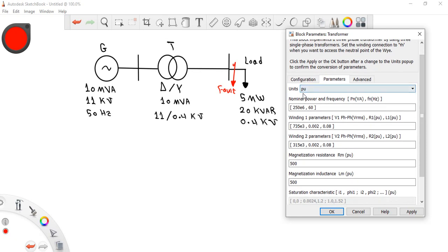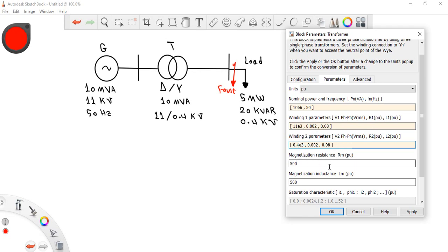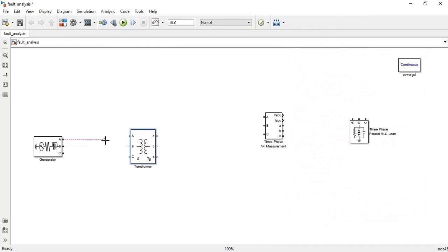In the parameters tab, set the nominal power to 10 MVA (10e6) and frequency to 50 Hz. For winding one, the line-to-line voltage is 11 kV, and R1 and L1 are kept at default values. For winding two, the line-to-line voltage is 0.4 kV. Keep the magnetizing resistance and inductance at their default values. Click Apply and OK, then connect the generator to the transformer.